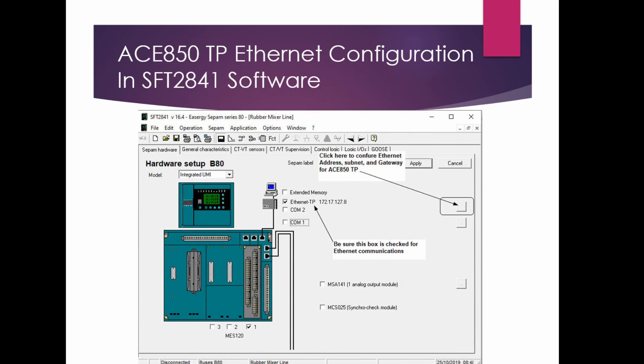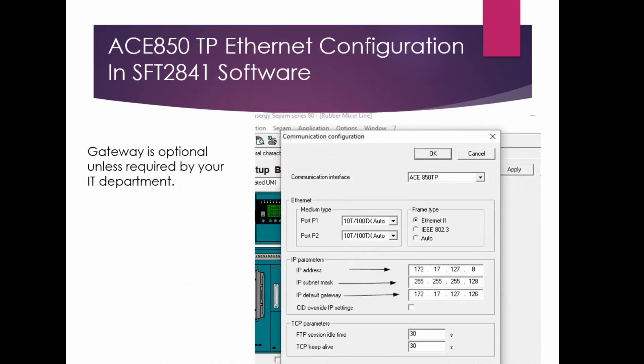For the ACE850TP module configured for Ethernet, click on the box to the right after you've chosen Ethernet. Make sure that box is checked or you won't be able to open the configuration block. Once it opens, enter your IP address and subnet mask. Whether or not you need a gateway will depend on your IT department — if your facility is operating on separate VLANs you'll most likely need a gateway. Check with IT.